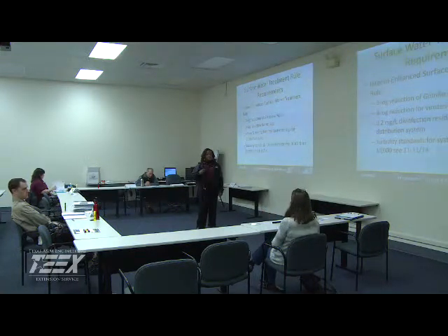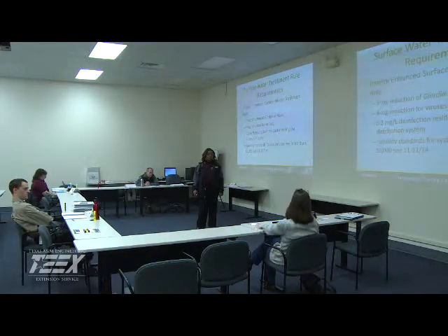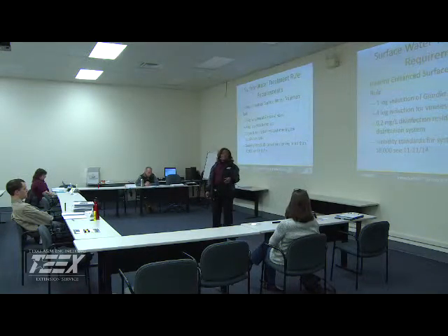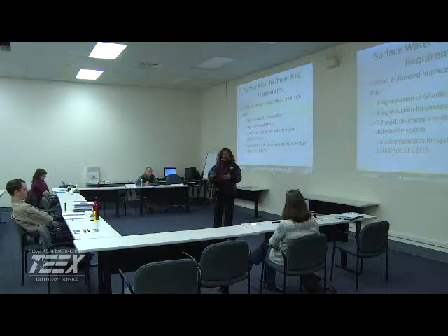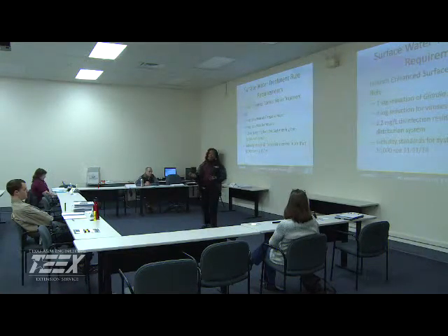Yes, ma'am. Please tell me, if a surface water system collects a total coliform sample and gets a chlorine residual less than 0.3 or 0.2 out in the distribution system, what should they do then? What should they do once they've collected? What we tell people normally to do, first of all, before we pull that coliform sample, we're going to check the chlorine. If the chlorine is beneath that 0.2, 0.3, we don't continue the process of collection, but we flush, make sure you've got well chlorinated water coming into that area, make whatever adjustments need to be made, and then go back and pull your sample.